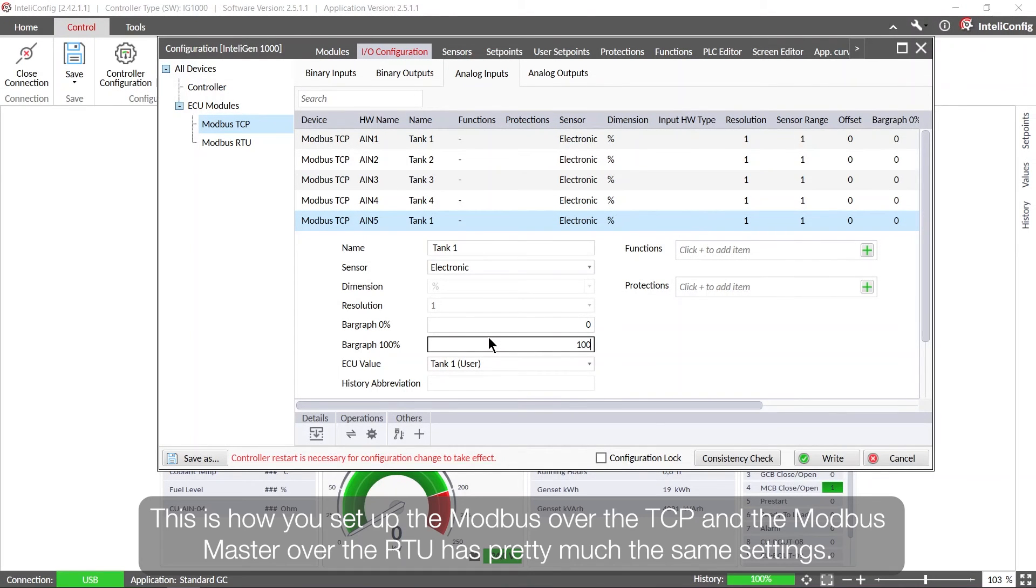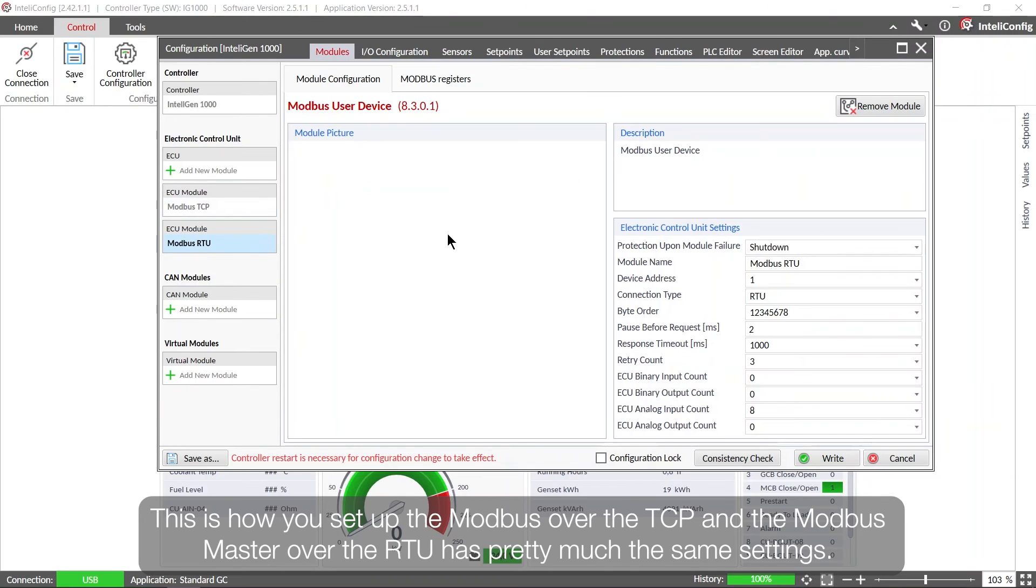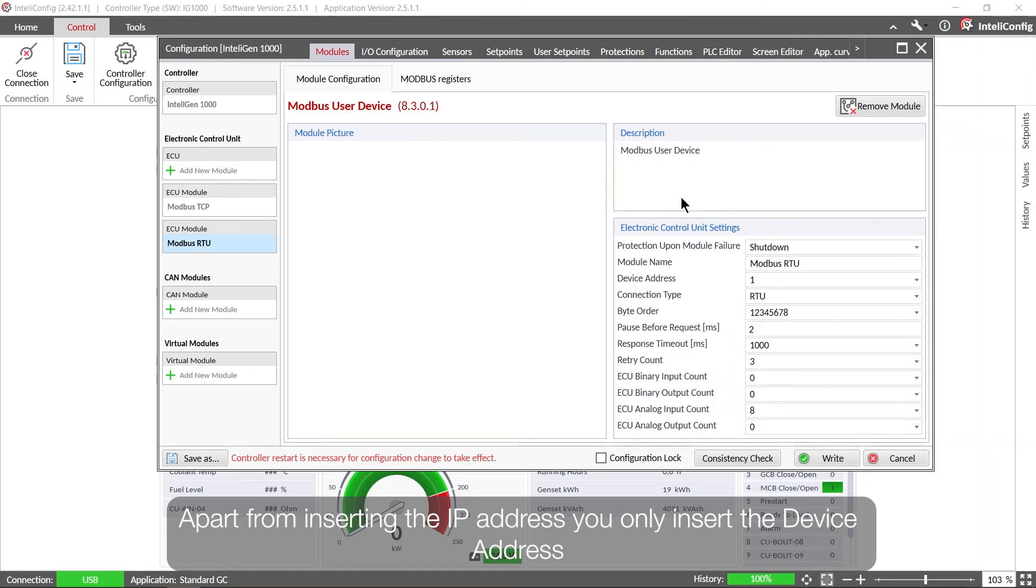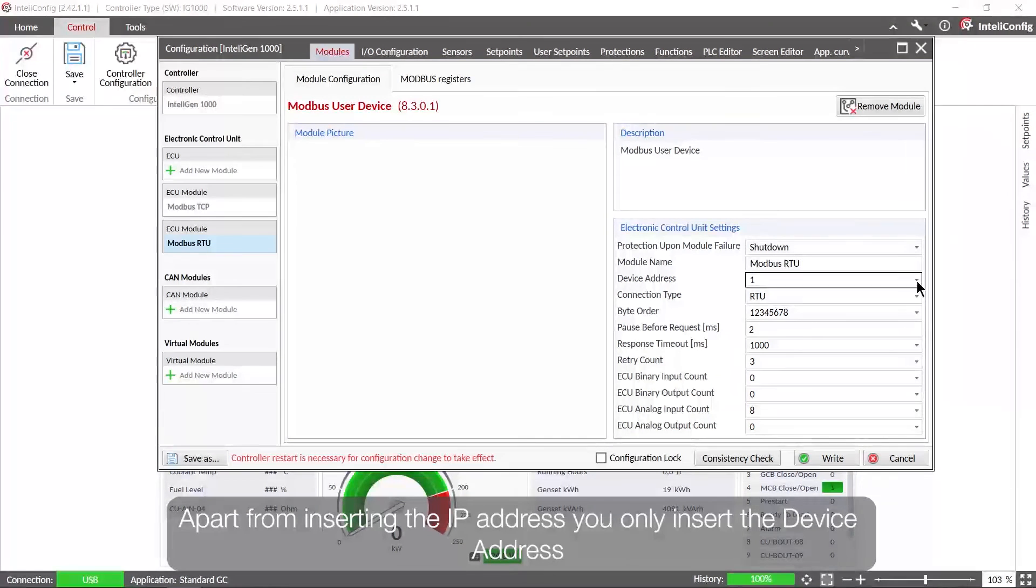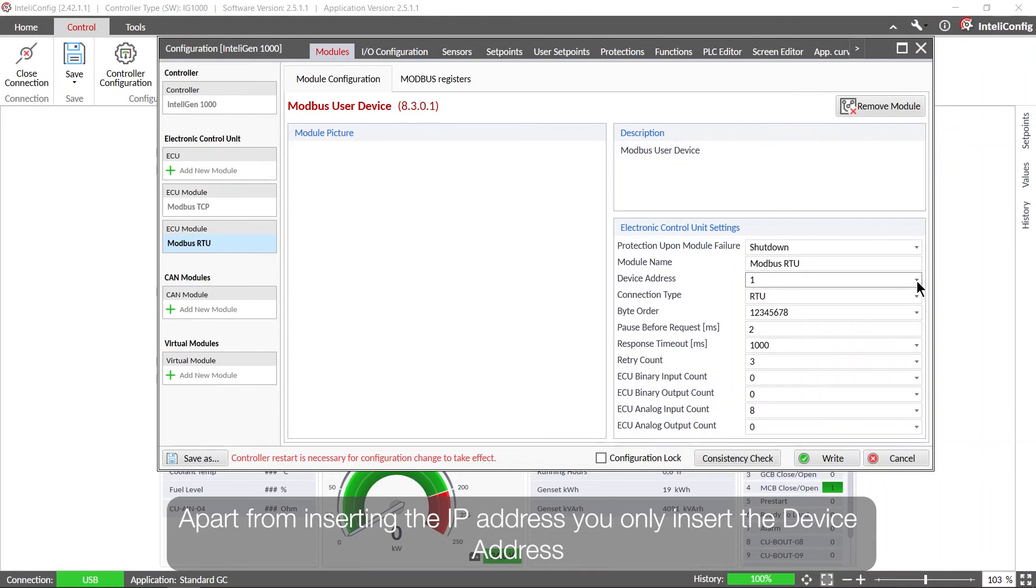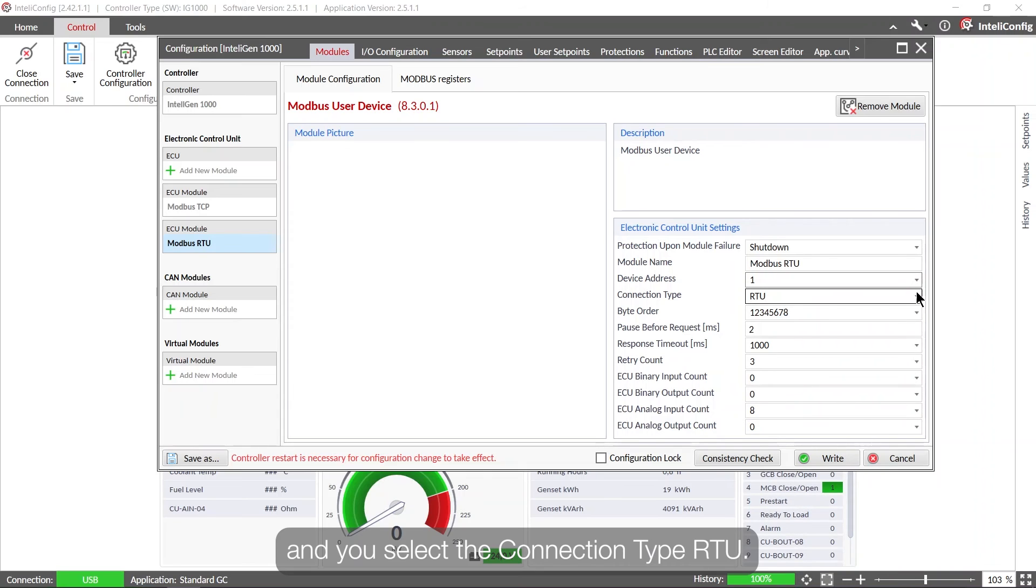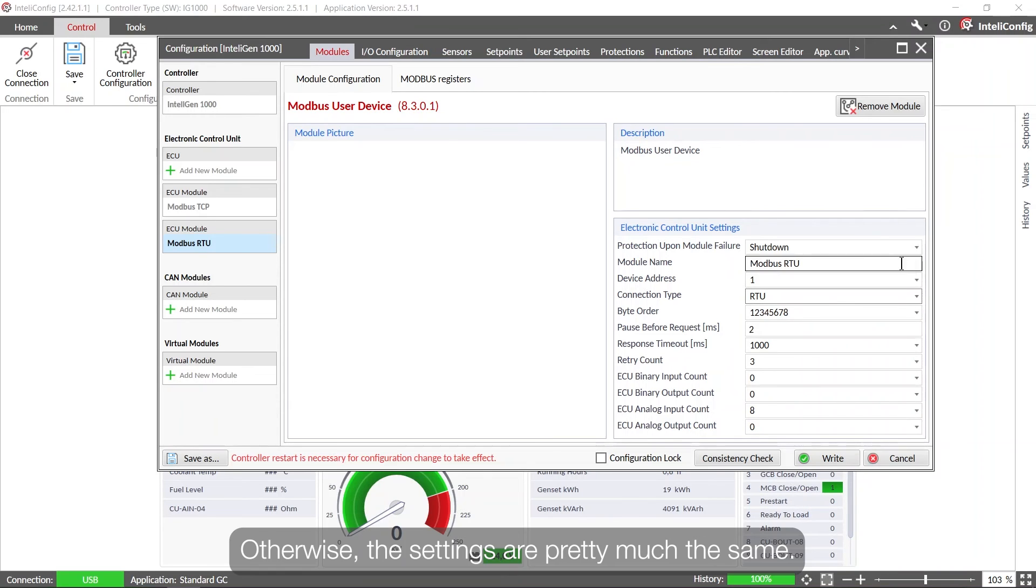So this is how you set up the Modbus over the TCP, and the Modbus master over the RTU has pretty much the same settings. Apart from the inserting the IP address, you only insert the device address and you select the connection type RTU, otherwise the settings are pretty much the same.